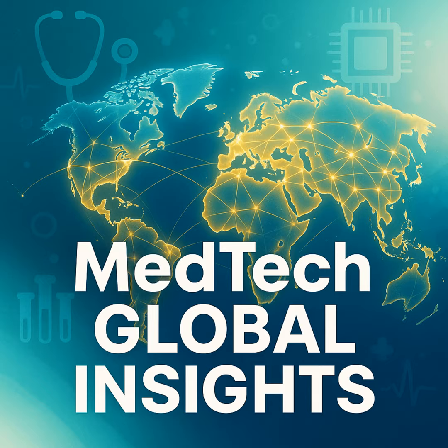Orthopedic implants are almost universally classified as high-risk medical devices. In the United States, they're typically Class 3, requiring a rigorous pre-market approval, or PMA. In Europe, the stringent medical device regulation, or MDR, also classifies them as Class 3. This regulation demands a higher level of clinical evidence and a robust post-market surveillance system that many legacy manufacturers were not prepared for. Companies now need a comprehensive lifecycle approach to compliance, not just a one-time approval.